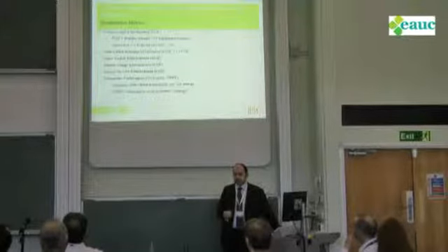So, quantitative metrics, well, there's a lot of these out there, but I'd say the industry standard, pretty much at the moment, is a very simple one. It's called Power Usage Effectiveness, or PUE. And essentially what it does, it takes the facility power and the IT equipment power. Basically, it's a ratio of facility power to IT equipment power.